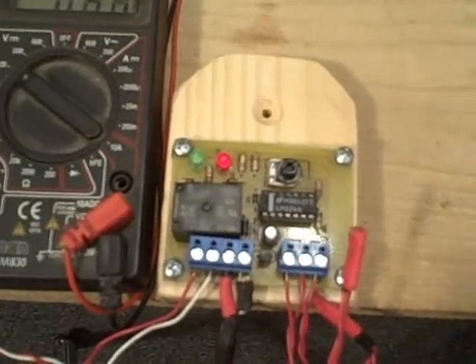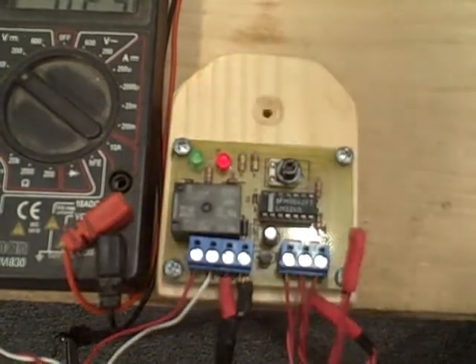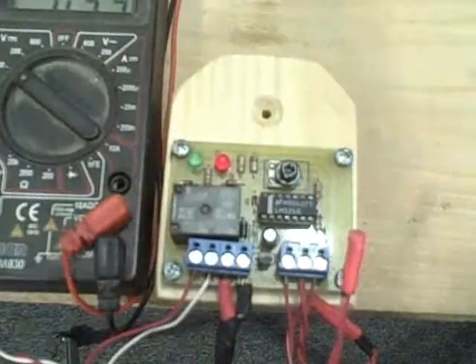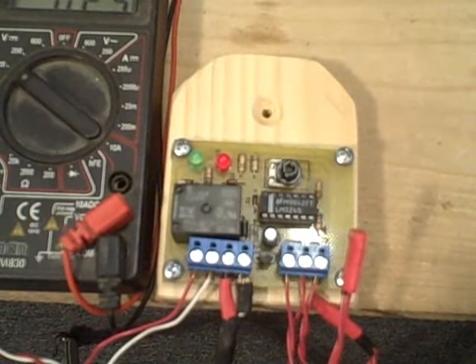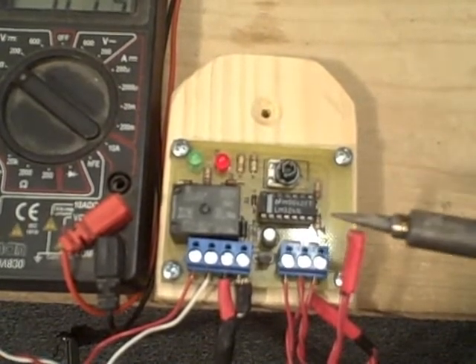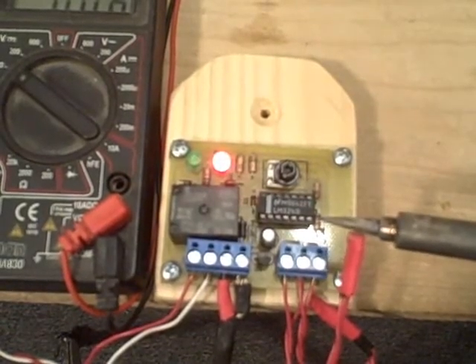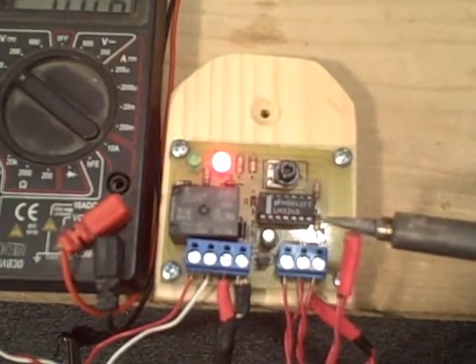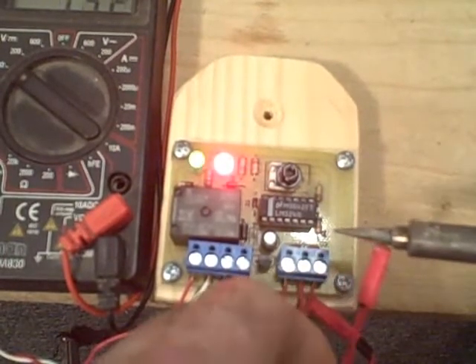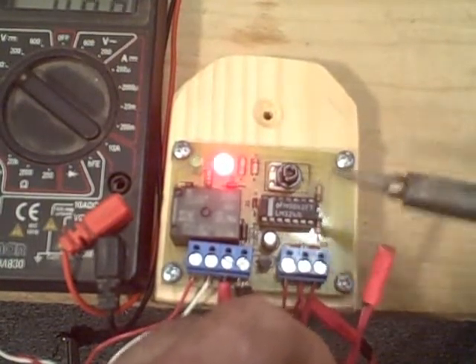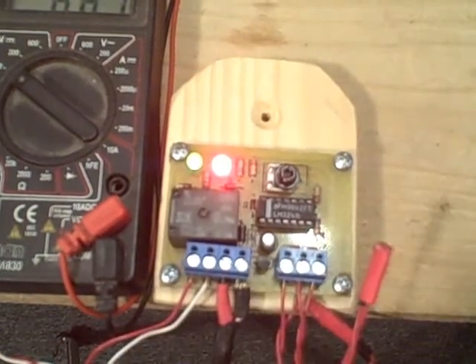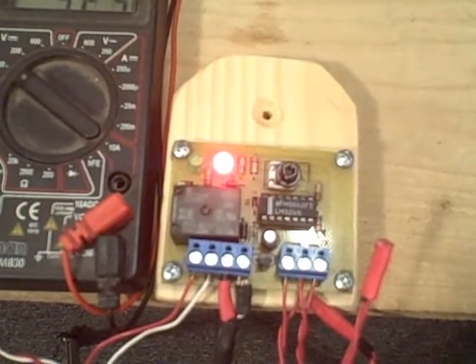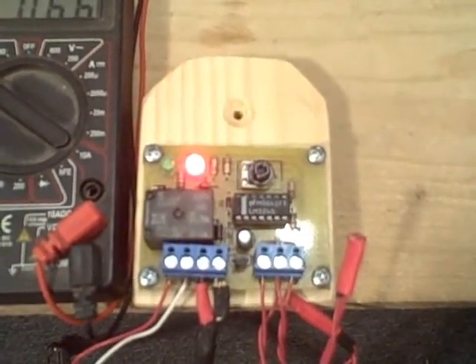Now it just came off. This can be adjusted. This is the differential pot adjustment. If we turn it totally counter-clockwise, you can turn the pump on. If we turn it the other way, the pump comes off, and it takes more heat to activate the pump. That red light, which we'll talk about in the next video, indicates the amount of heat that's available. The more heat I add to the probe, the hotter it gets. Eventually, it should come on. It comes on at a very high temperature. That's a differential temperature of maybe 30 to 40 degrees. But you notice it doesn't stay on very long because that cools down pretty quickly.